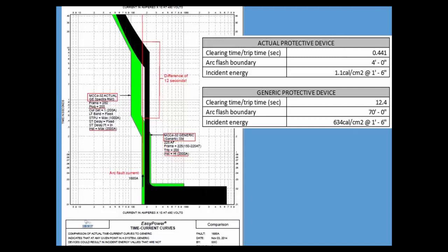Here's a time curve showing a generic device. EasyPower can give you some generic devices, so we have to be aware of the pros and cons of that, the generic setting versus the actual setting. We took one out of one of our analyzed systems, and this one shows a 12-second difference in clearing time between the generic setting and the actual real device.